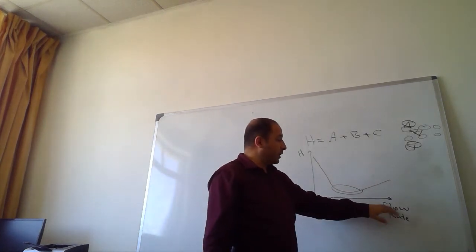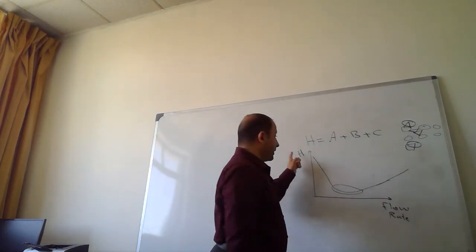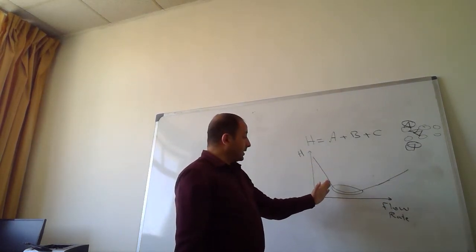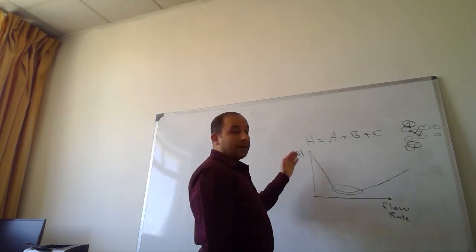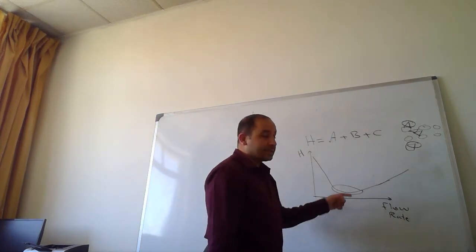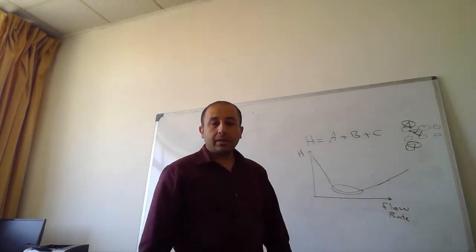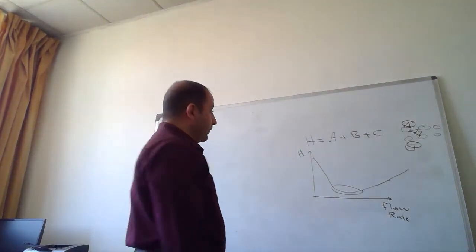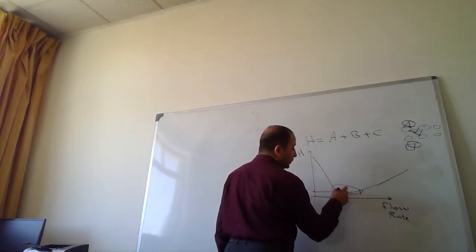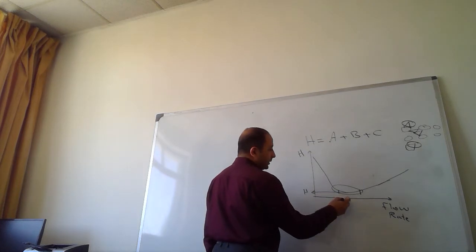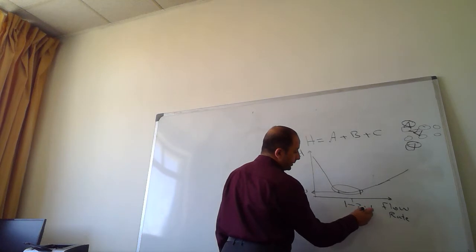So if you increase the flow rate drastically, then you have what? You have an increase in height plate. At the same time, in contrast, if you reduce the flow rate, then you will also have a high height plate. But there is a minimum here, in which the flow rate will be accepted due to low height plate, and usually it is from 1 to 2 mL per minute.